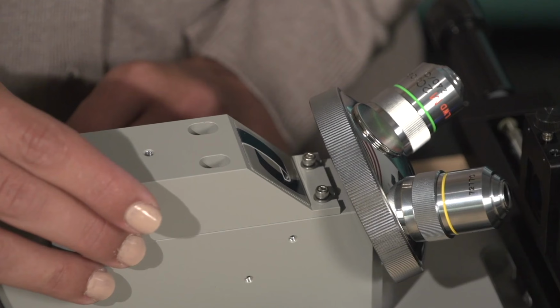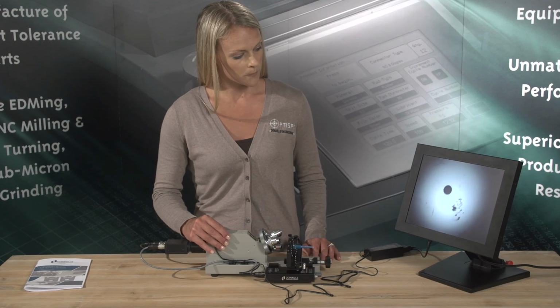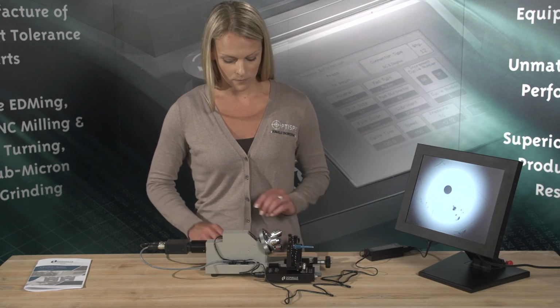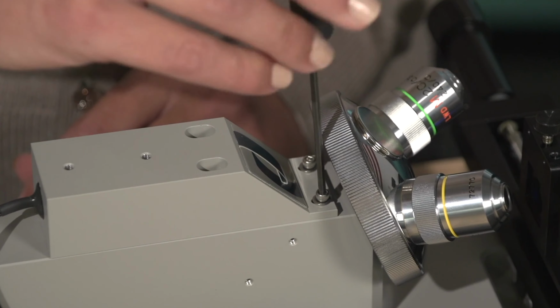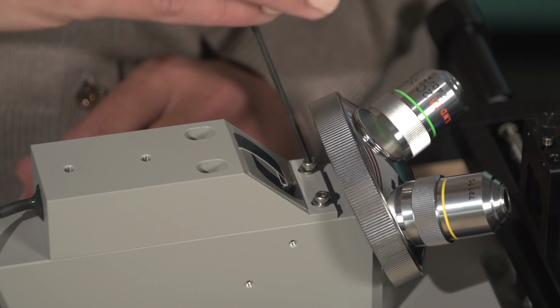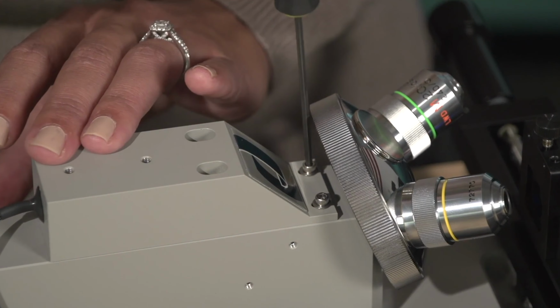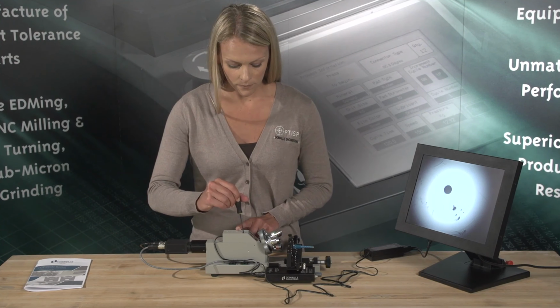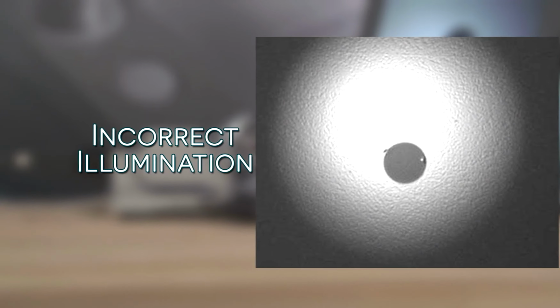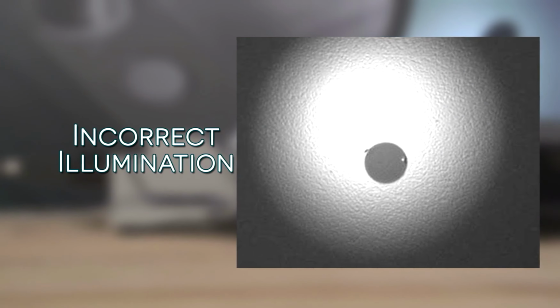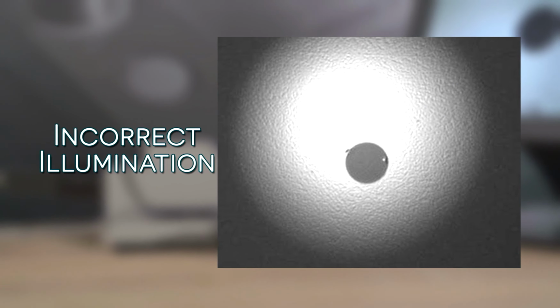Using a 3/32 hex wrench, loosen the 4 socket head screws holding the light block. While viewing a fiber on the monitor, slide the light block around until the greatest amount of light is centered over the fiber. Retighten the 4 screws. Incorrect illumination. Notice how the light is towards the top of the screen. Correct illumination. Notice how the light surrounds the fiber. Light scratches can now be easily detected.